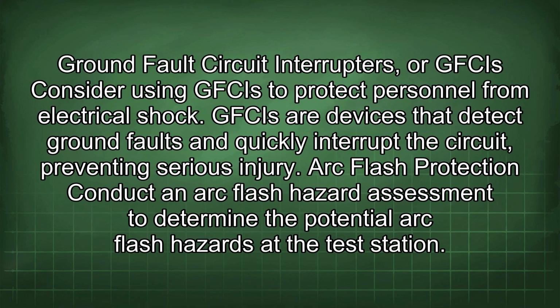Ground fault circuit interrupters, or GFCIs: consider using GFCIs to protect personnel from electrical shock. GFCIs are devices that detect ground faults and quickly interrupt the circuit, preventing serious injury. Arc flash protection: conduct an arc flash hazard assessment to determine the potential arc flash hazards at the test station.